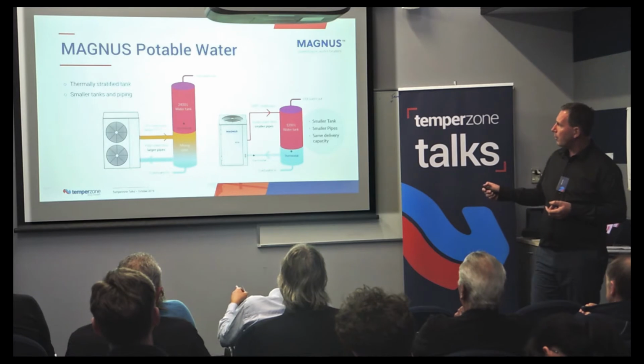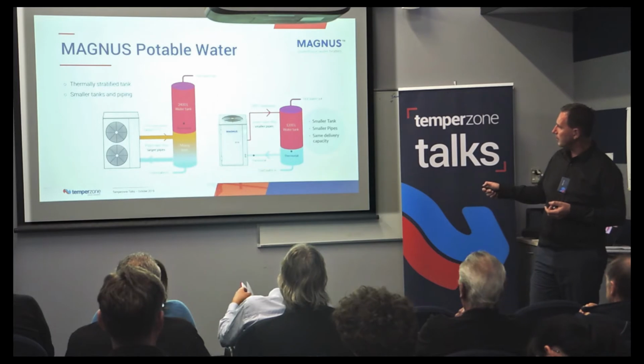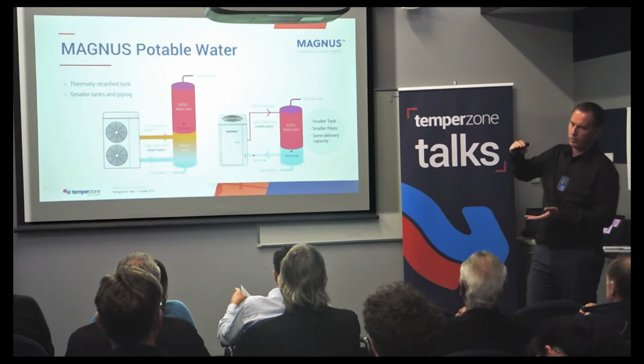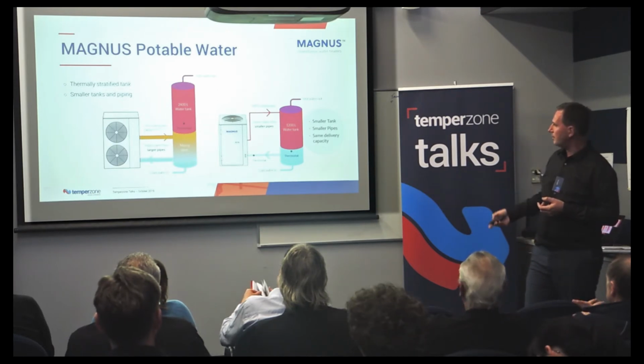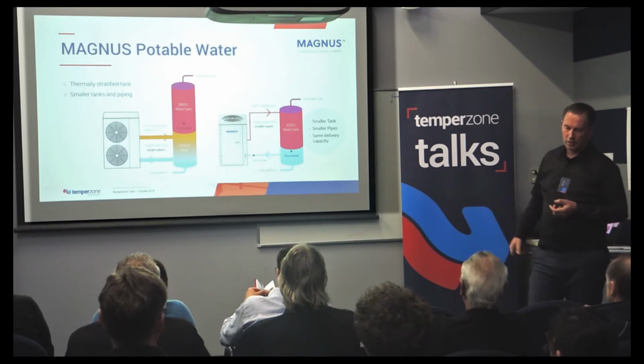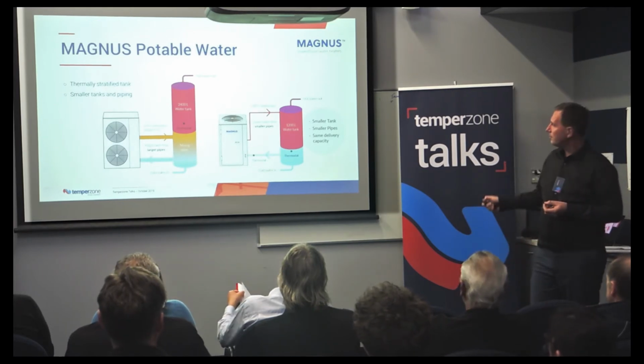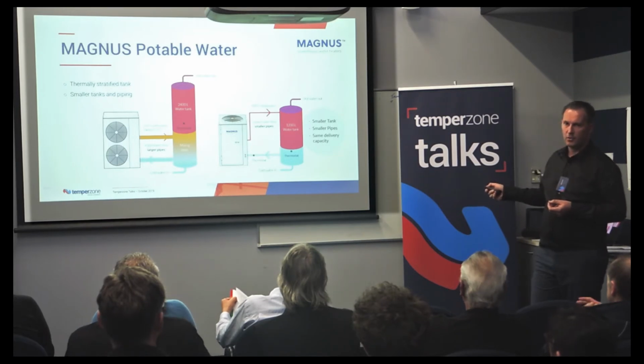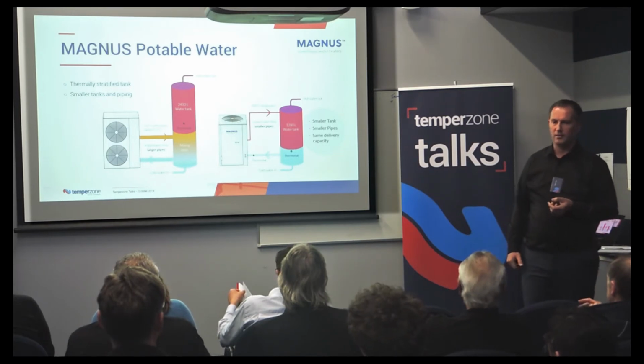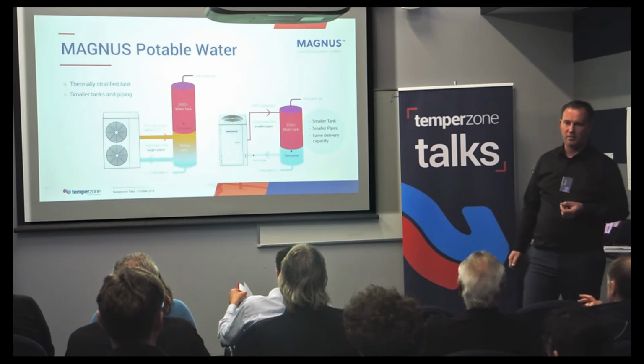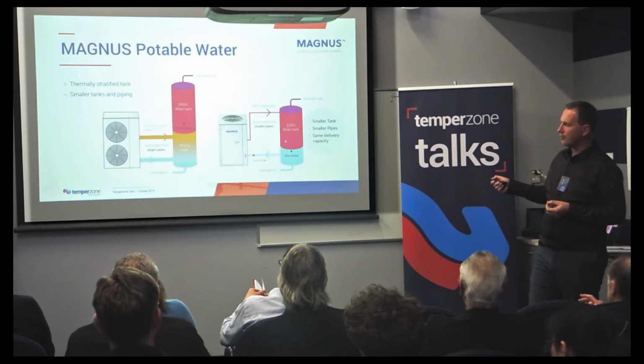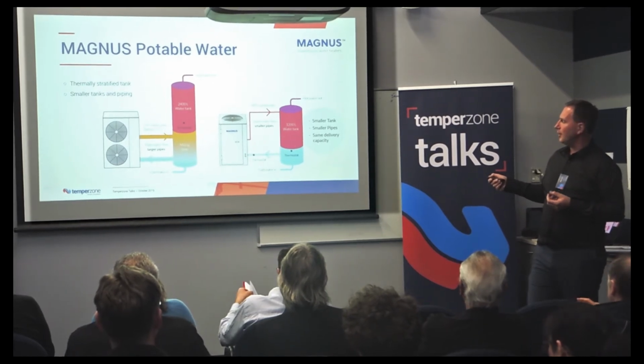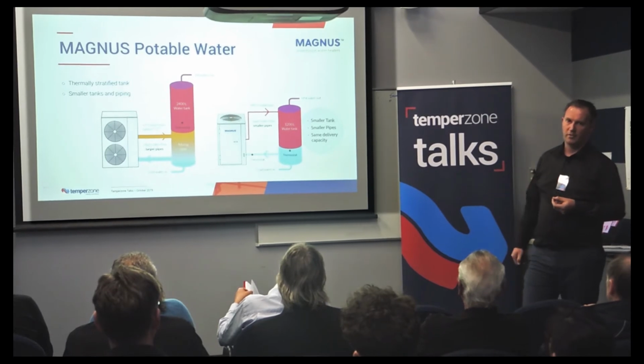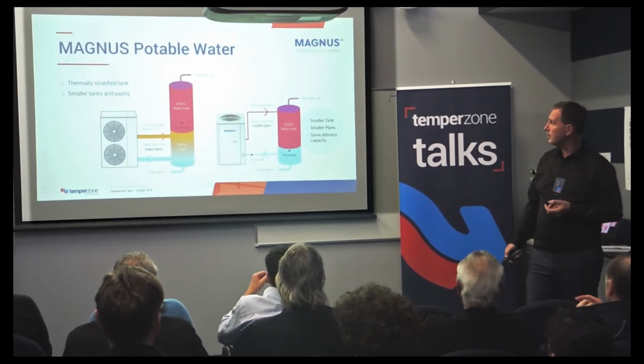So, for our potable hot water, we take the cold water in from the bottom, we heat it to 60 degrees in a single step, and we float this hot water on the top down in our tanks. Now, a unit like this will do around 500 litres per hour, so that we can extend that storage by up to 1,000 litres in every 2-hour peak demand period, and around a third of the unit cost is offset by the reduction in storage that you need.